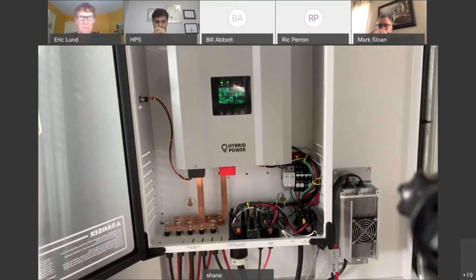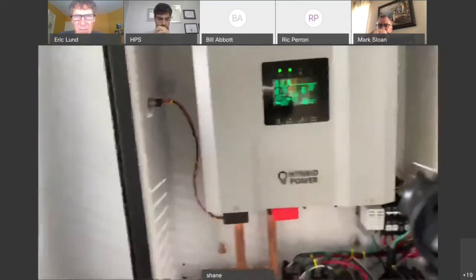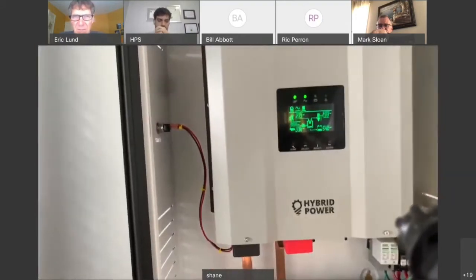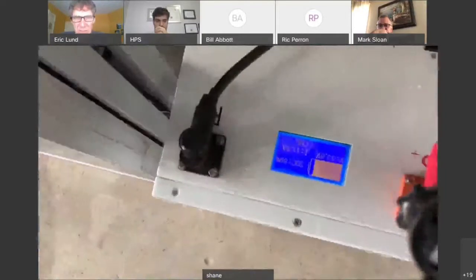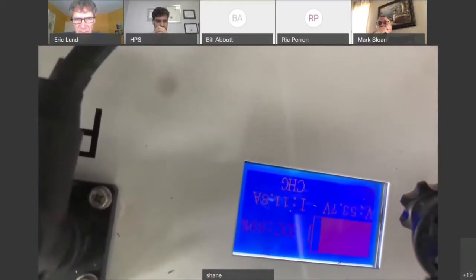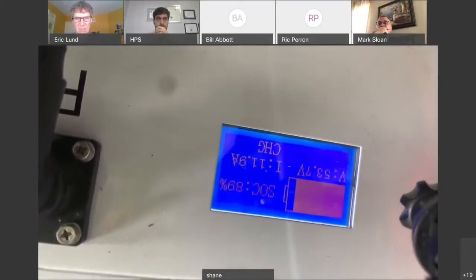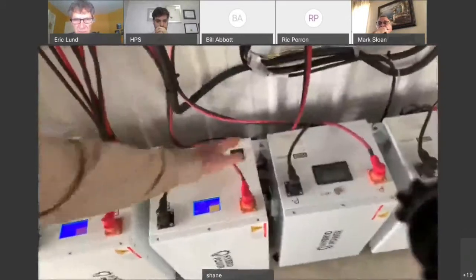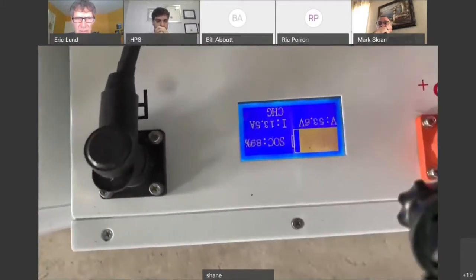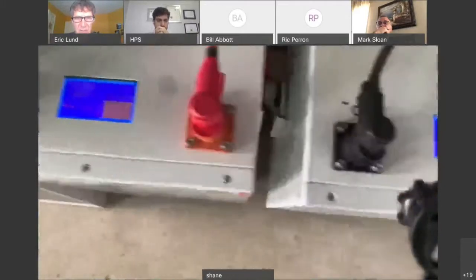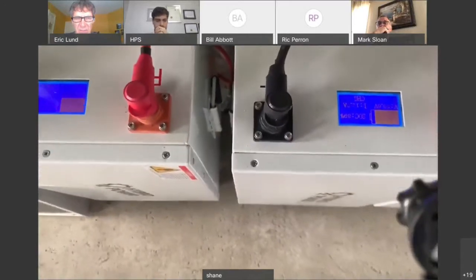So just transfer it over to AC line mode. It's going to come on because it's going to be in charge mode. And you're going to see right away we are charging at 11.8 amps. So then if I have the other battery going on, it is charging at 13 amps and 7 amps. So it splits the difference between them on the BMS of what's available.